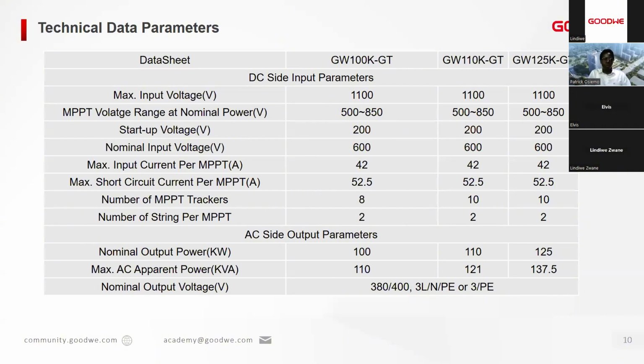A quick run through on the datasheet for the GT. You can see that the maximum input voltage is 1,100 volts, with MPPT nominal power between 500 and 850 volts. And with as little as 200 volts, you are able to start up. As we've mentioned before, the maximum input current for MPPT is 42 amperes, with a max short circuit current for MPPT of 52.5 amperes. Then for the 100, you have 8 MPPTs, for the 110 and 125, you have 10 MPPTs, and across all of them, you have 2 strings per MPPT.